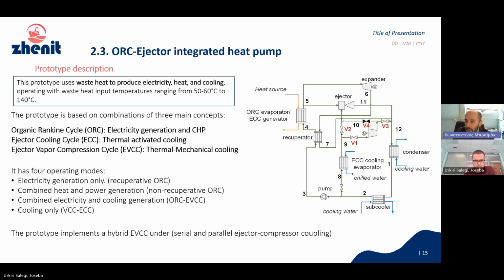And we have another way to couple these two devices. The second way is to have a serial coupling. So in this case, we have the vapor leaving at 0.9, and this vapor is sent first to the compressor, and then after leaving the compressor, it is applied to the ejector. So the compressor and ejector are connected in series, and the advantage here is that the compressor operates at a smaller pressure ratio, so the COP of the vapor compression cycle is improved, and also the ejector performance is improved because it entrains vapor at a somewhat higher pressure, so it has an easier capability of entraining more flow and increasing the cooling output of the whole system.